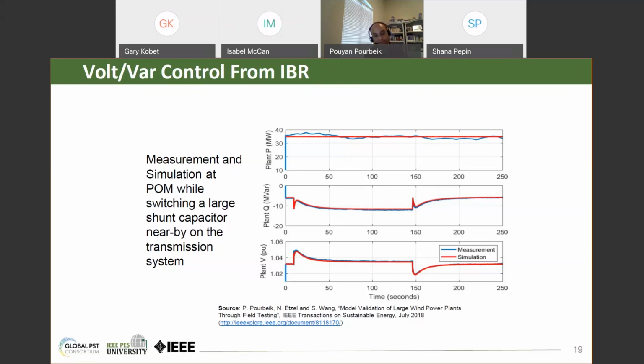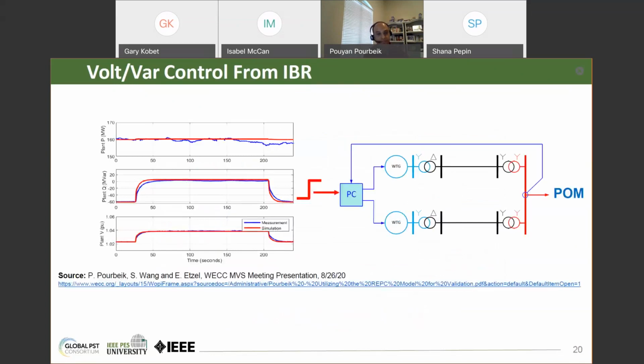It's not a problem. And if we go to the next slide, here's another example where you have a larger plant. There are two large collector systems coming onto two substation transformers, and you have an overall plant controller, and you can see where we give a reference step to the plant controller and very quickly change voltage up and down. No problem. And the current models can mimic all this, and they did in the previous example as well.